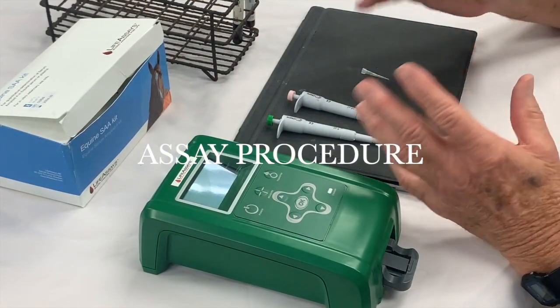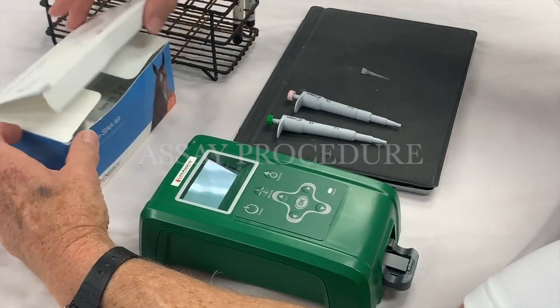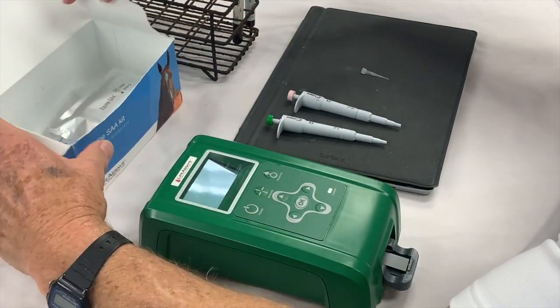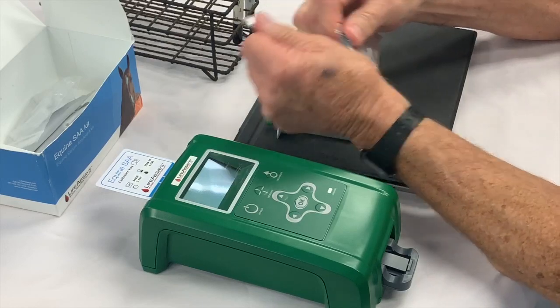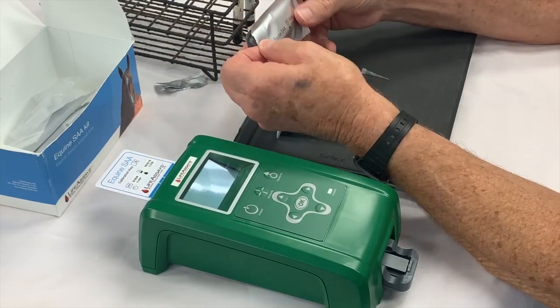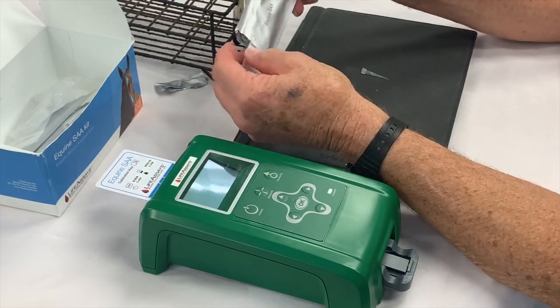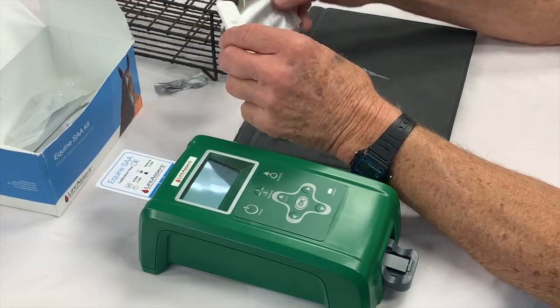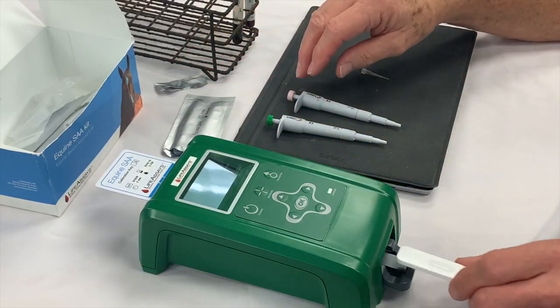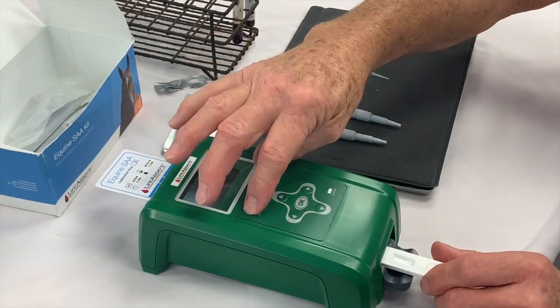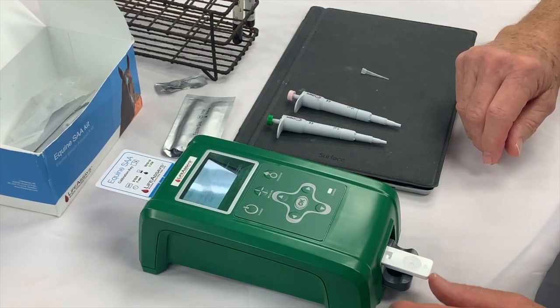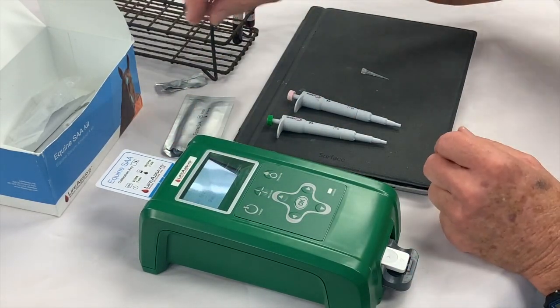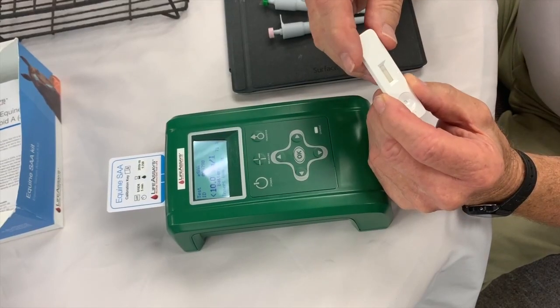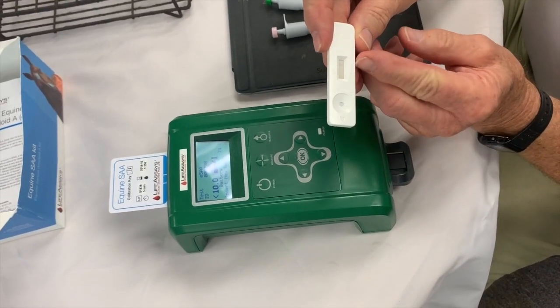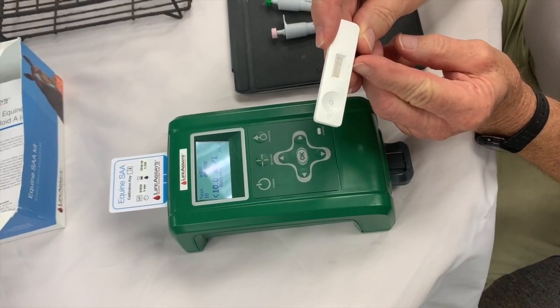Assay procedure. Number 1, turn on Magnia Reader. Number 2, open the aluminum test pouch. It has 1 cartridge and 1 clear plastic disposable dropper. Insert the cartridge into the reader so that the small arrow on the end of the cartridge is visible and pointing toward you. The sample well marked S will remain outside the reader.